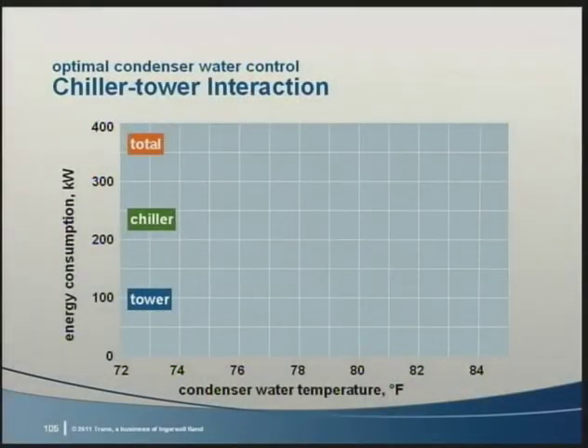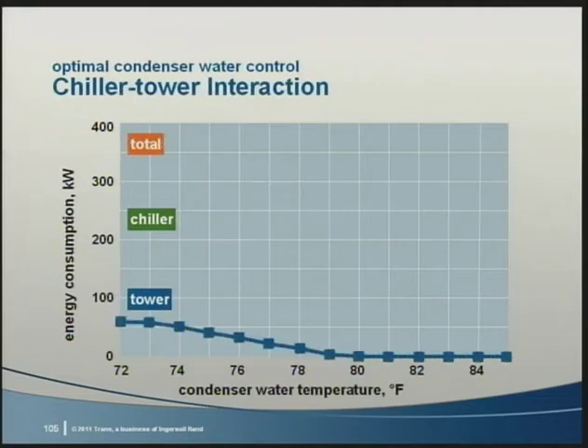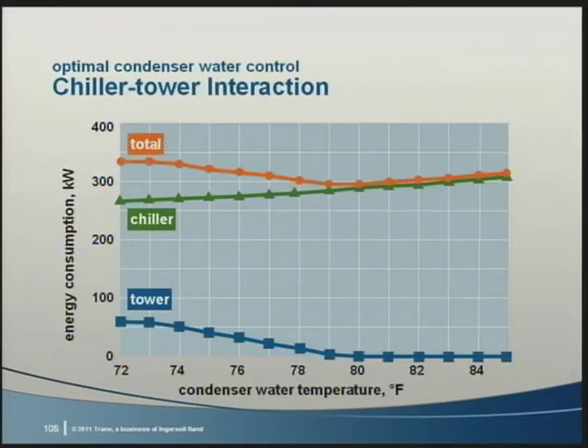Let's look at an example of the concept, then discuss savings available. Here we have a chiller operating at 60% load when the outdoor air wet bulb temperature is 65 degrees. If the tower fans are operating at full speed, 73-degree water can be provided. If at half speed, 79 degrees. The chiller power rises at the elevated condenser water temperature. But what the chiller system owner pays for is the sum of chiller plus tower energy use.